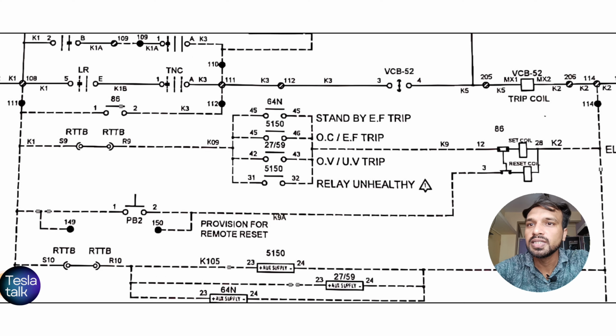First, this one is the standby earth fault trip. It's a standby earth relay with contact 64N, and the 5150 is the overcurrent and earth fault trip. This overcurrent relay protects the system by tripping during overcurrent or earth fault conditions. And there is also an OV and UV trip. This relay trips the breaker if there is an issue with the voltage levels. If the voltage goes above the rated voltage or below the rated voltage, then it will generate a trip command to trip the breaker.